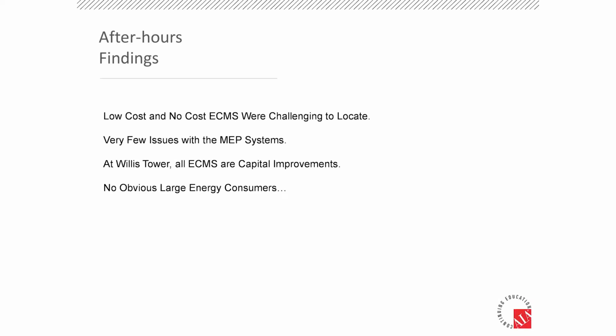So these are typical items, but there's some things we see as we go through the building. One, there were very few low-cost and no-cost ECMs. They were really on the schedules. They were on the set points as much as they could. What they could change, they had. What they tried to optimize, they could with the systems they had. We saw very few issues with the MEP systems. So we didn't see many issues with the belts on the units. Dampers operated well. And filters were changed on a very regular basis. Ductwork was in fairly good condition for a 40-year-old building.